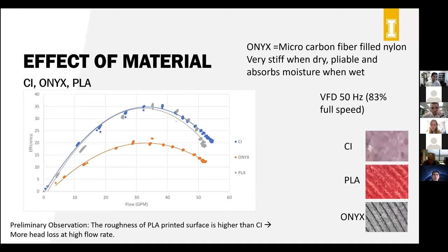On the Onyx side, you can see that efficiency is almost comparable in the low flow zone, but as flow increases, the efficiency decreases significantly. And we think that's because of the surface roughness. If you look at the zoomed out image of these three materials, cast iron, PLA, and Onyx, this 3D printed material is much rougher than the cast iron itself. And that's what it is showing here. It is consistent with all other speeds as well. As flow increases, the decrease in efficiency is significant.